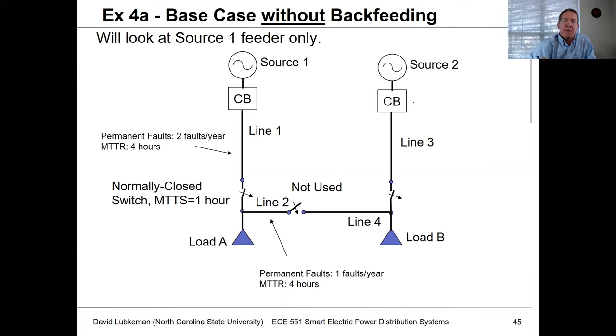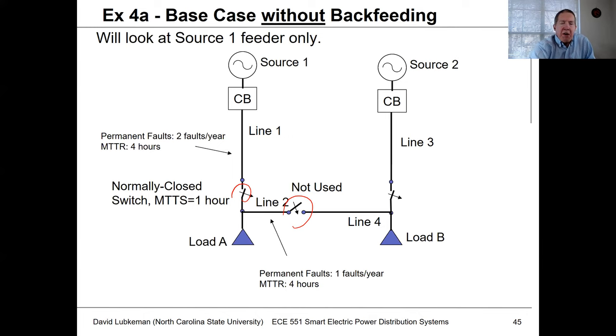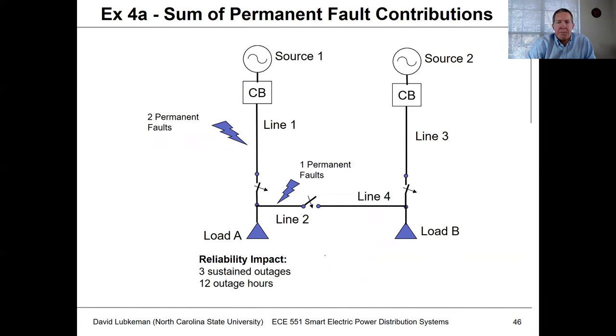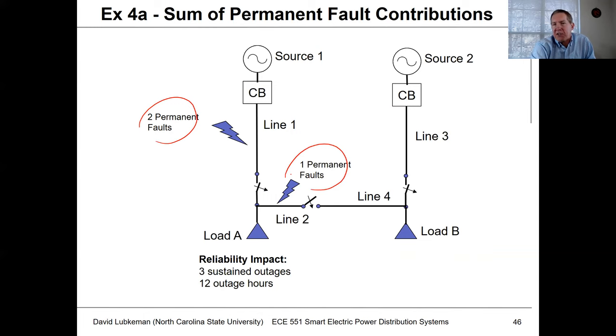For the base case, I assume the sectionalizing switch is always closed and operable in one hour if needed. I've got an open tie switch that we're not going to use yet. Because of the failure rates, we have two faults per year on line one and one fault per year on line two. Summing the permanent fault contributions: since load A has no back-feed and is directly connected to line two, any permanent fault results in a sustained outage at A — three sustained outages, four hours each, gives a total of 12 outage hours.